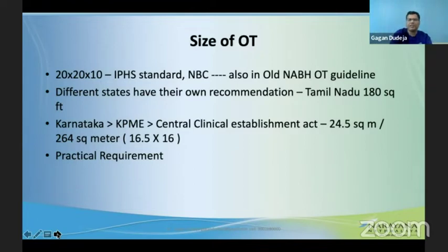In Tamil Nadu it is 180 square feet. Delhi is around 150 odd square feet. In Karnataka, the KPME Act says we follow the Central Clinical Establishment Act, which puts ophthalmology OT into category 2, requiring 24.5 square meters, roughly 264 square feet, about 16 by 16.